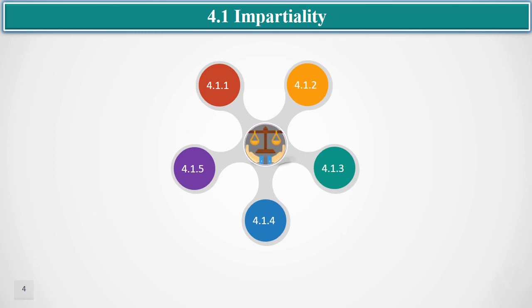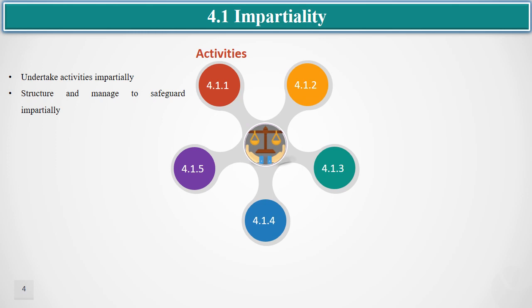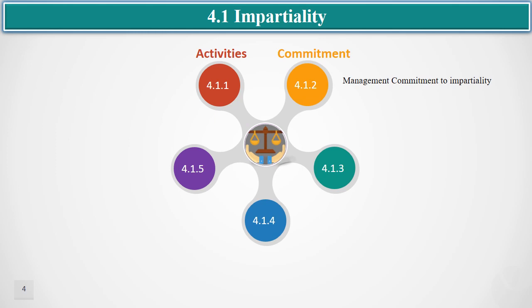Now let us discuss the requirements. Clause 4.1, which is dedicated to impartiality, has five sub-clauses. As per sub-clause 4.1.1, all laboratory activities shall be conducted impartially. The organization structure of the laboratory and laboratory processes to perform operations shall be managed in a way to safeguard impartiality. For example, if the laboratory is part of a bigger organization, the laboratory head shall not report to the production head from where samples are being received.